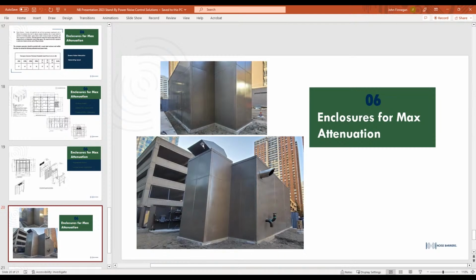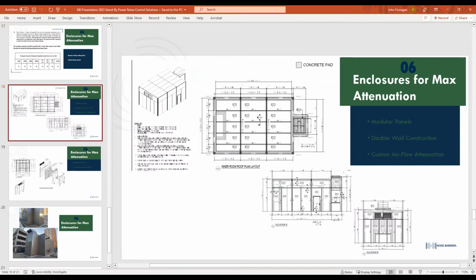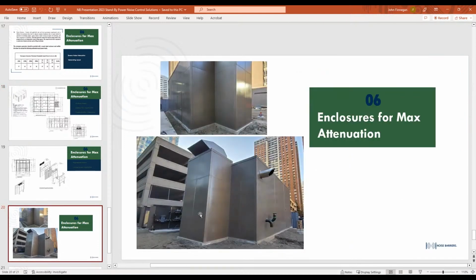Here's how we'd handle that exhaust. The air's going through here, and as you saw in this drawing, we have tube axial fans towards the base of that big exhaust tower, sitting right in here, with silencers above that discharging out of a weather hood. Anywhere you walked within 3 feet around this unit, you had to be 45 dBA at 100% load, as the spec required.